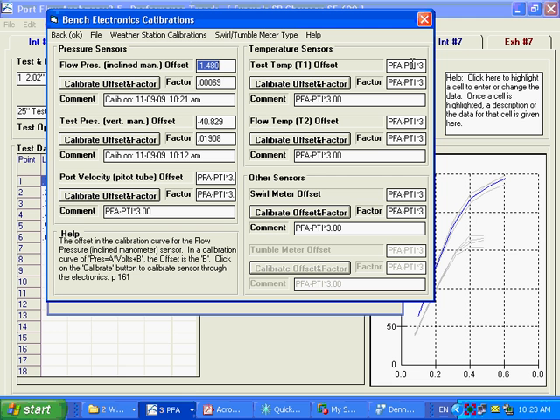But I would suggest just use the factory calibration. I think you're much better off, and even though it reads a couple degrees off, you don't really care what the exact temperature is. It's the difference between the two temperatures that's important. If both of them are reading 3 degrees high, the temperature difference between the two is still the same. So I would use factory calibrations here.